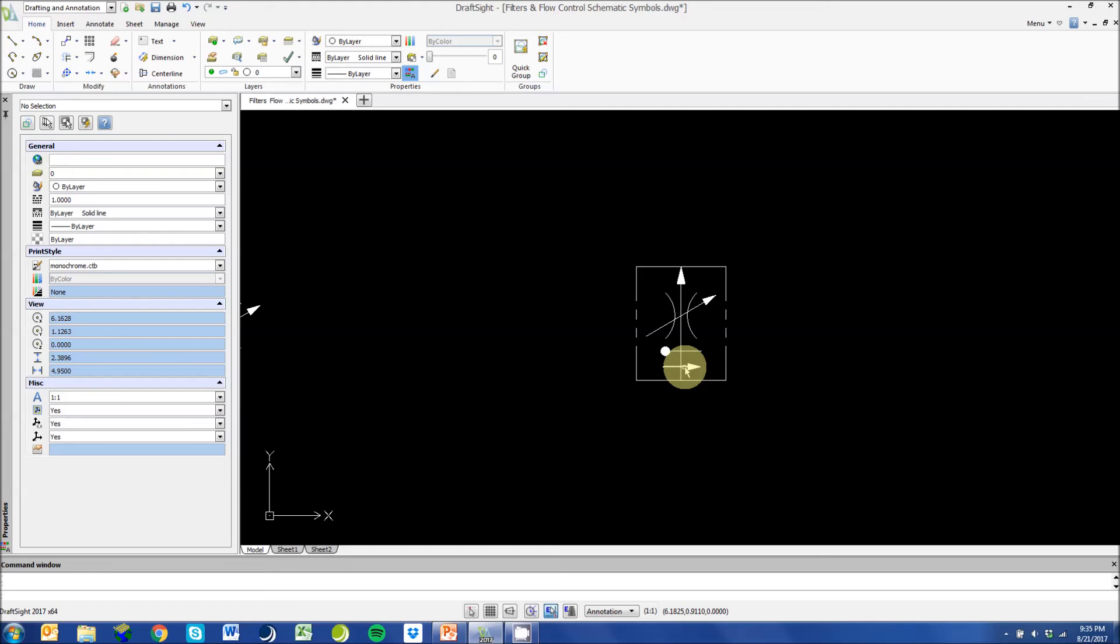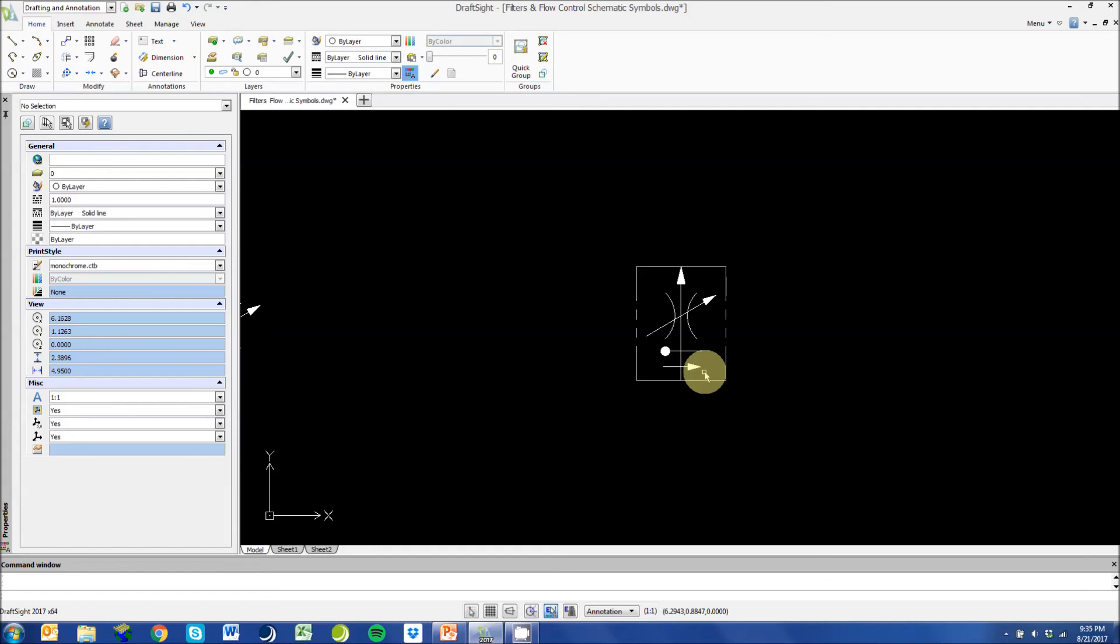The second additional symbol is a sideways arrow. This means your valve is pressure compensated. In similar fashion pressure variations in your system will not change the amount of flow through the valve.